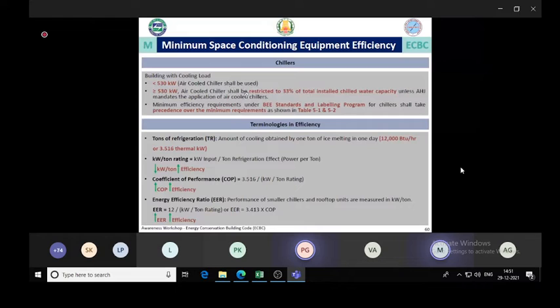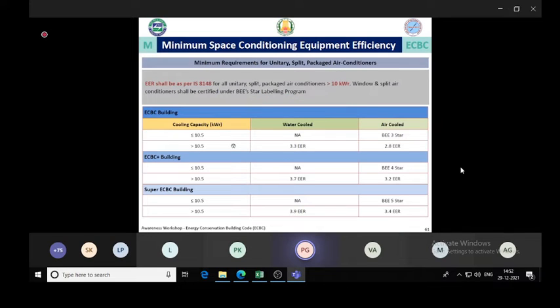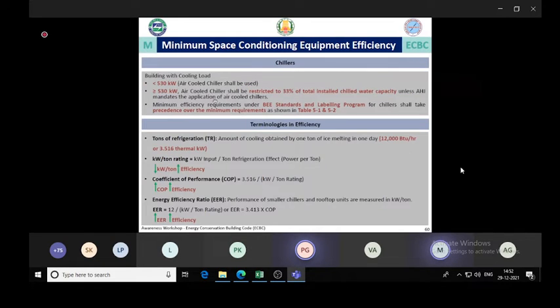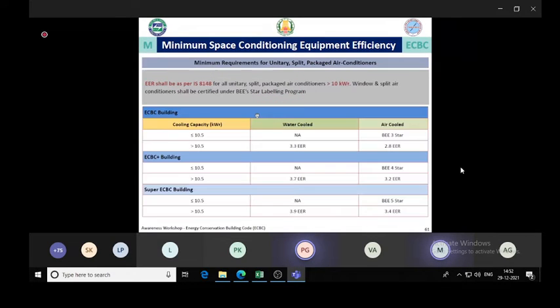So that is one significant requirement here, but there is an exemption in case the local authority, for example here in Chennai, if the CMDA allows you to use air-cooled chillers, then you can use them. Because of water shortage or other constraints, if there is an exemption from the local authority, then in that case you can use air-cooled chillers. Right. And similarly, for each of the equipment, in case of chillers, it is chillers. In case of VRF systems, it is VRF systems. The minimum efficiency to be followed, the COPs and IPLV values are given.